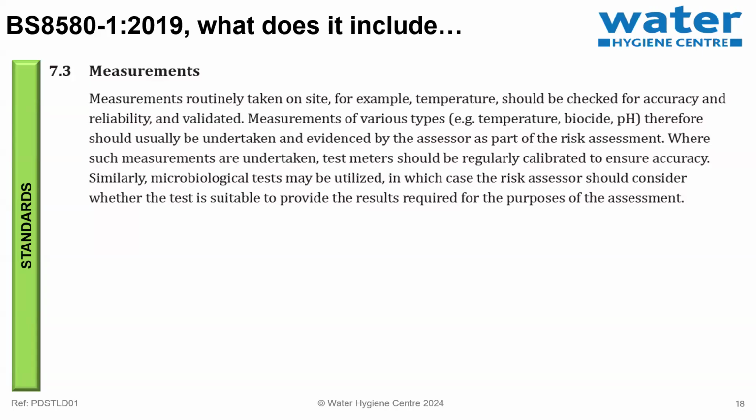We need to monitor temperatures. And the way that we monitor temperatures is really key. The person completing the routine checks, have they been trained? There are different types of thermometers: immersion, contact, dual gauges, for example, BMS systems. Do they know how to use them correctly and where to record the data? When was the thermometer last checked or calibrated? When did we last calibrate the gauges on the vessels, and how reliable is that data?